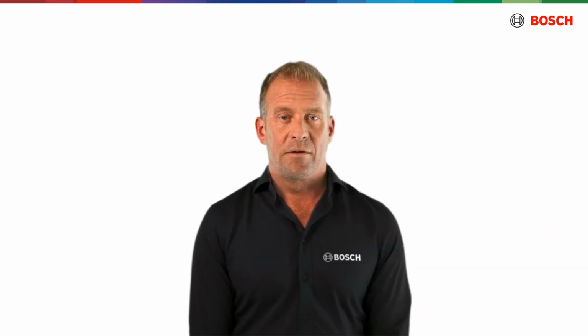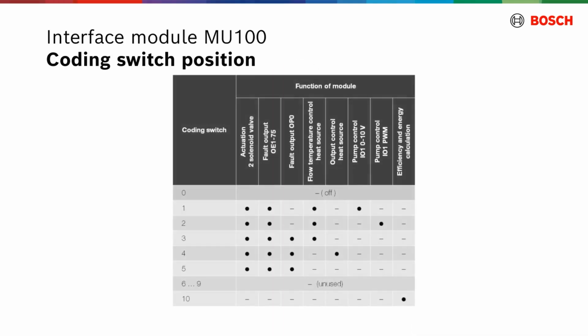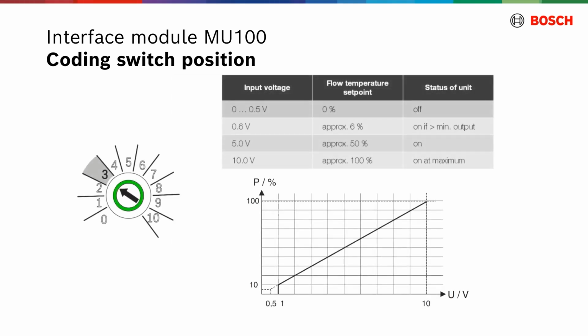To ensure the proper functioning of the connected heating circuit, the valid position of the coding switch should be chosen. Two control strategies are possible when the heating system is controlled by the building management system. With the coding switch in position 3, the module MU100 controls the output of the boiler. The connected heat source is enabled and disabled according to the signal from BMS setting up the required output. There is a linear relationship between 0 to 10 volt input signal from BMS and the required performance of the boiler.